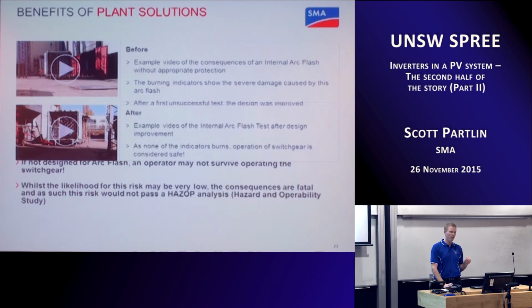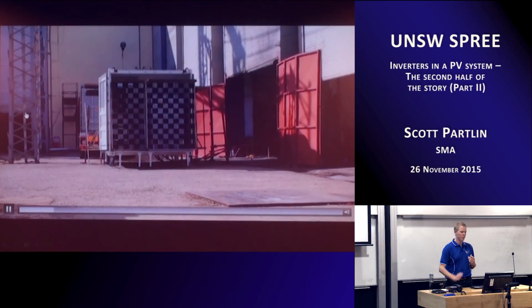So what I've got here, on that previous slide where I showed a solution that had the inverter, transformer and switchgear, we've got two examples. One is where this arc flash protection has been disabled, and another where it's active. Just to show you what would happen to, say, a plant operator turning on the switchgear, and potentially there might be a ground fault on the AC side or some sort of short within the transformer. Without arc flash protection, this is what would happen.